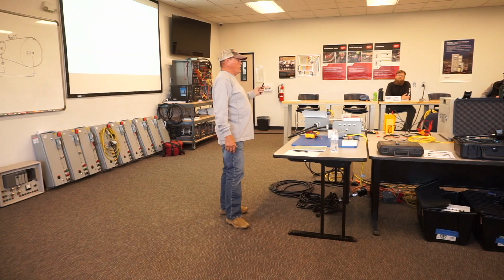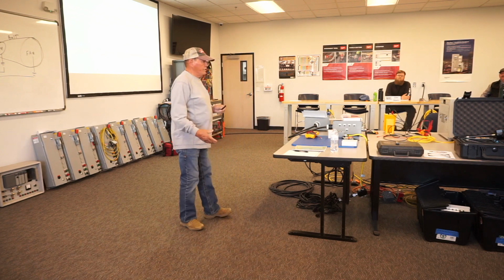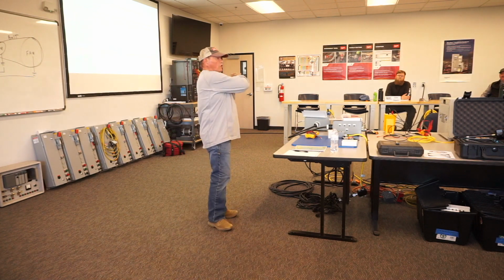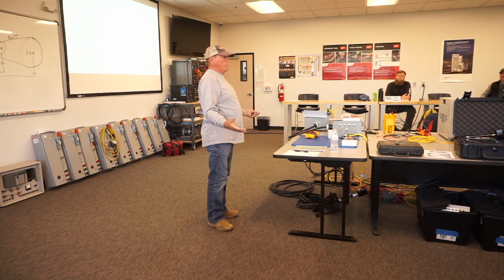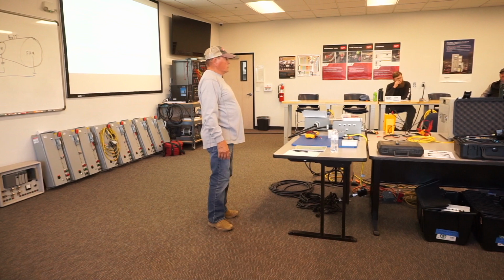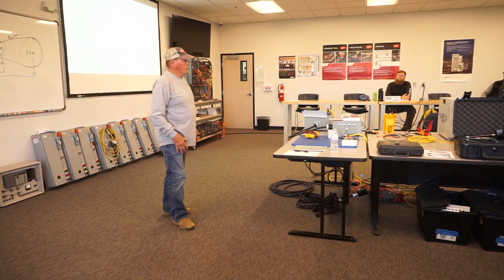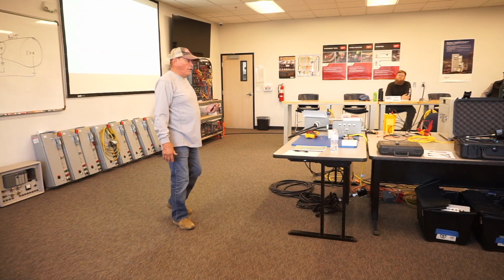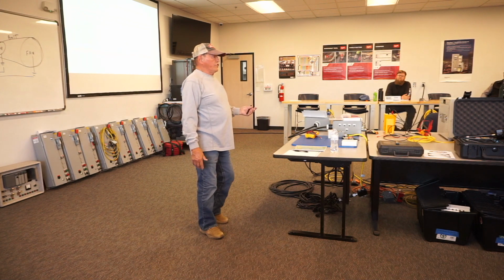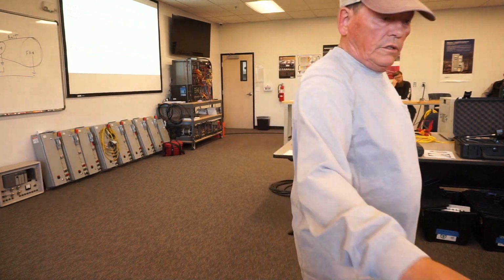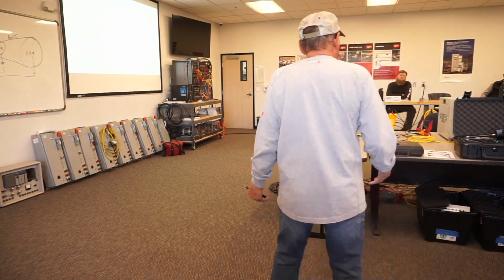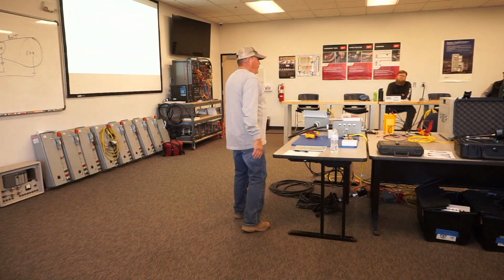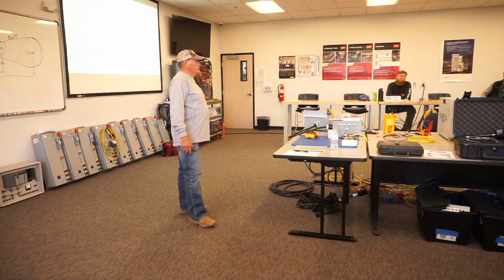When the Sparks Police Station converted their cars to Bluetooth connected computers and equipment inside their cars, and they parked underneath the parking structure, which was all lined with solar panels, their Bluetooth equipment went berserk. So I put a filter on the DC bus and the AC bus to filter out that EMI that was traveling through on the DC side of the system. Well, the DC side of the system is where I'm losing all of this. All this melting is happening on both the AC and the DC side. And you'll see when we get to that section the damage that can occur to our electrical equipment. It's amazing how much destruction is going on in the PV world.